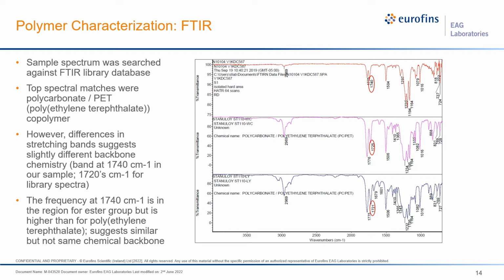Here on the top, we have three spectra. The top one is of the actual isolated hard part of this medical device. And then we have some spectral library matches for a polycarbonate PET copolymer. Comparing the spectra, we can see that there's a lot of spectral overlap and similarities between them. However, if we zone in and look at this peak that's at about 1740 in our sample, it doesn't quite match up to the peak in our reference spectra that's at about 1720. This corresponds to an ester-type functional group that's on the polymer backbone. So this may suggest that the material is some sort of a polycarbonate polyester mixture, but it may not actually be PET.